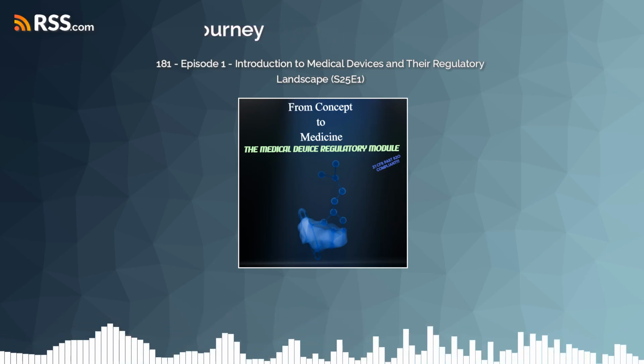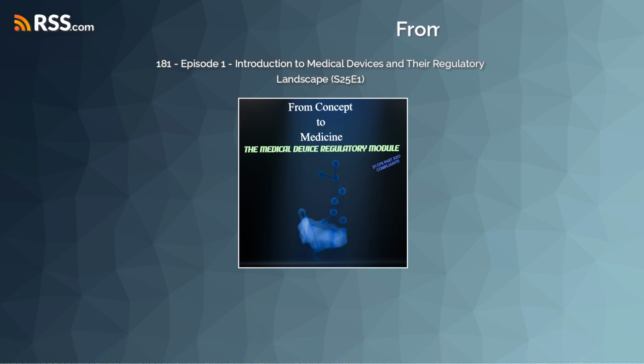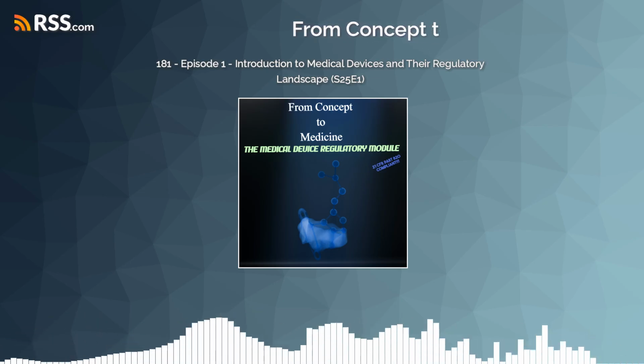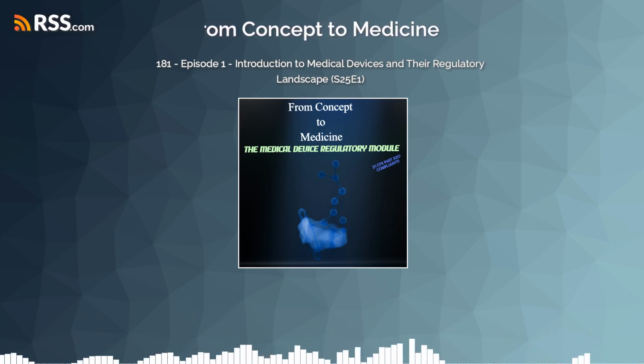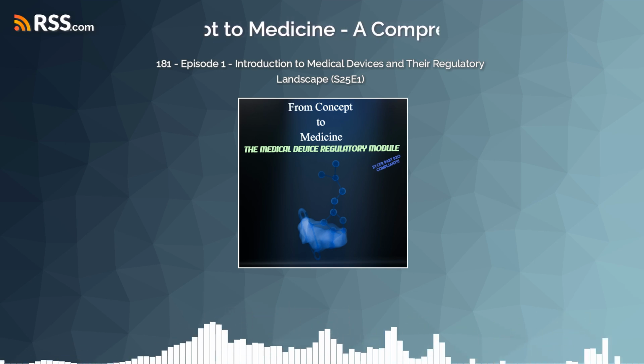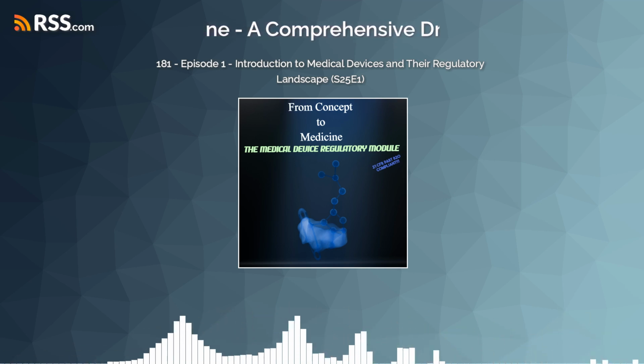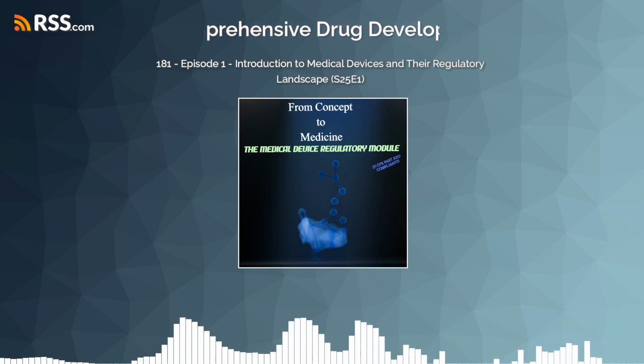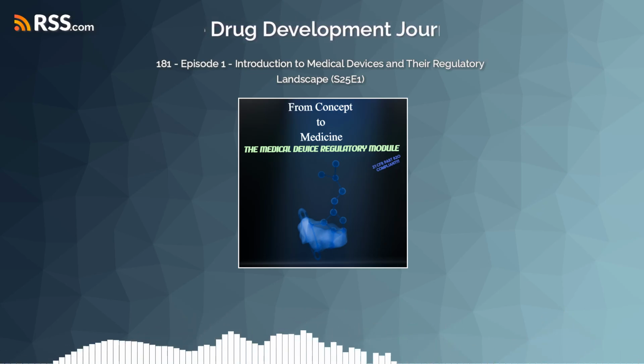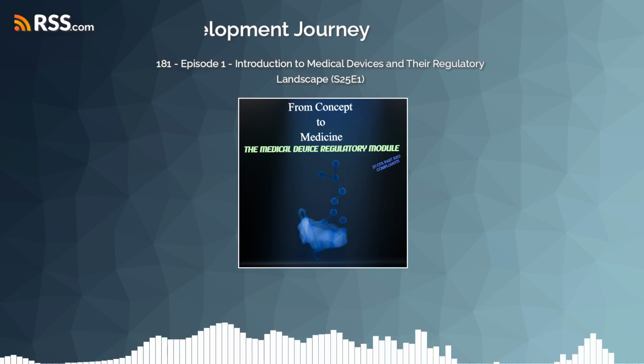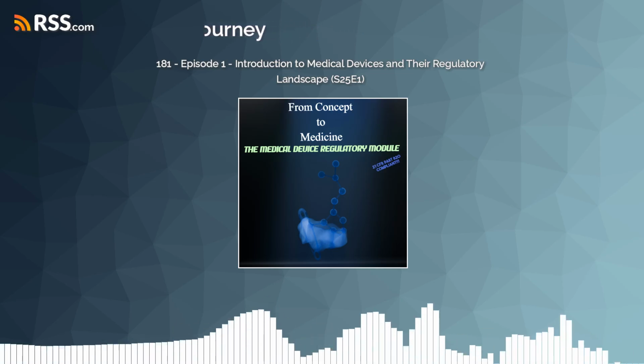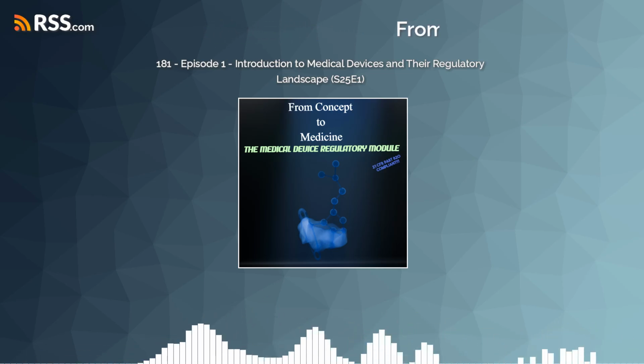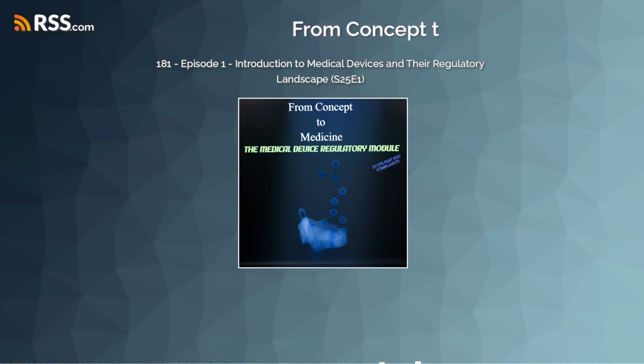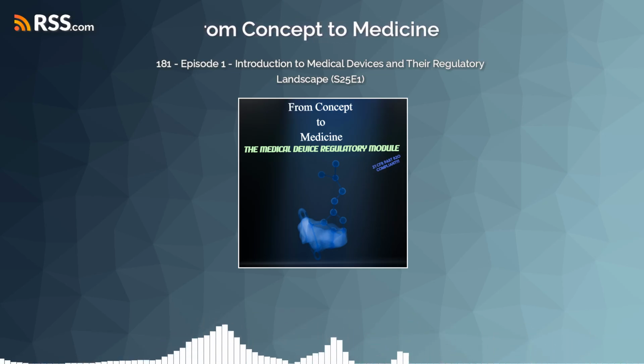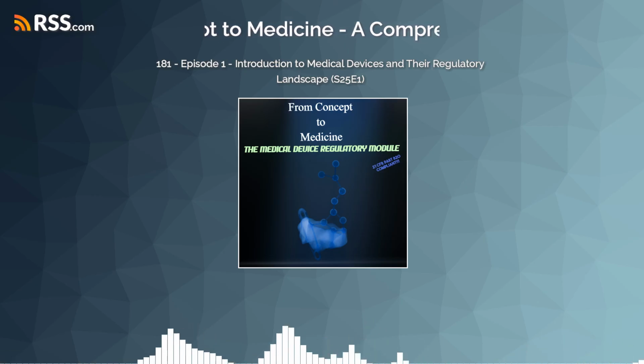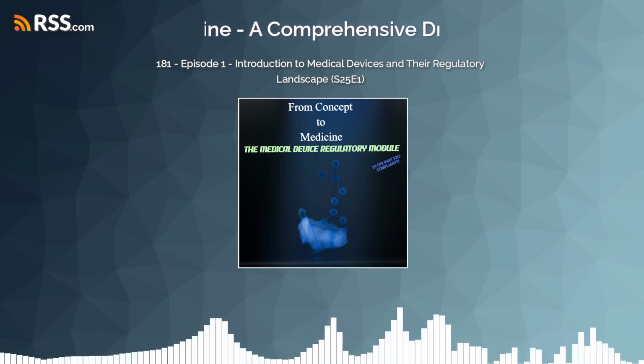What are the actual how-to for manufacturing once the design is locked? That's where the Device Master Record, or DMR, comes in. The DMR is essentially the definitive recipe or blueprint for manufacturing the device. It's derived directly from the design specifications in the DHF. The recipe. Got it. And for production and process controls, the QMS ensures devices are manufactured precisely according to that DMR recipe. This means documented instructions, standard operating procedures, SOPs for every step.